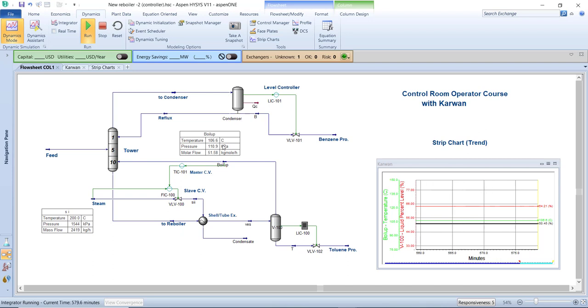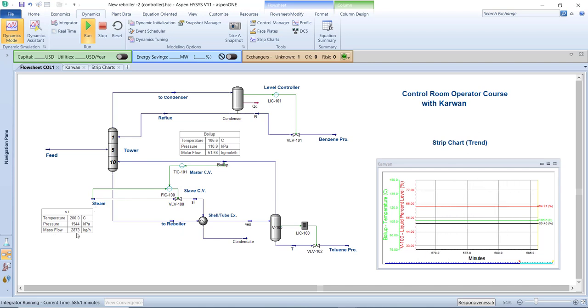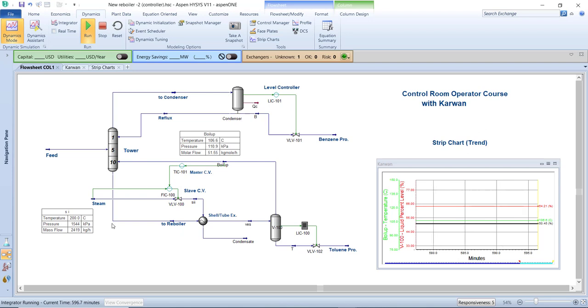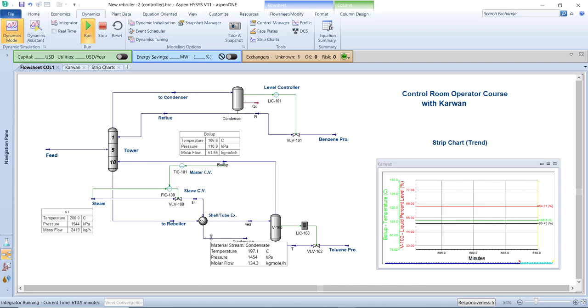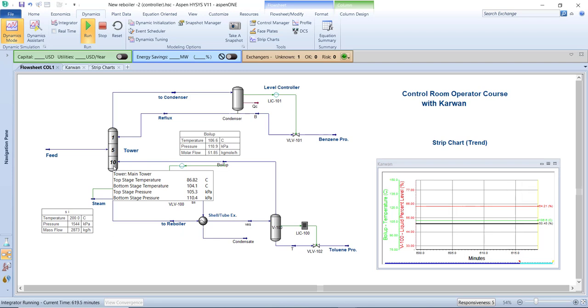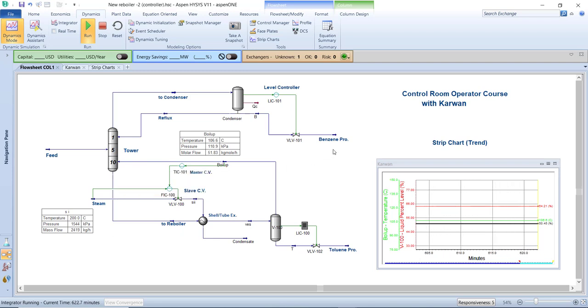If you look at the steam mass flow, before it was lower but now it has increased — because we need more steam flow through the heat exchanger. The steam temperature is 200°C, while the desired boil-up temperature is about 104.1°C, so to increase the boil-up temperature returning to the tower, you must send more steam flow through the heat exchanger. This increases the boil-up line temperature back to the tower. I hope this video is clear. If you want to join my courses, contact me. See you in the next video — goodbye!